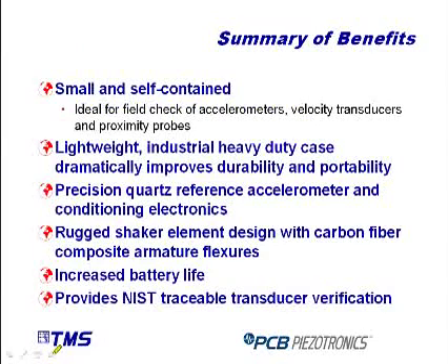A summary of the benefits. We've talked about a handful of these, but a couple of the ones that we haven't talked about to discuss here. The reference accelerometer that's built into the unit has been upgraded to the same ICP Quartz reference accelerometer that's inside our air bearing shaker, and that dramatically improves the stability of the measurements and results that we see on the front display. We've also upgraded the conditioning electronics built into the box from a fairly old kind of charge amp and through-hole component design of 20 years ago or so to all solid state and surface mount electronics with digital processing, all kind of state of the art from today's technology.